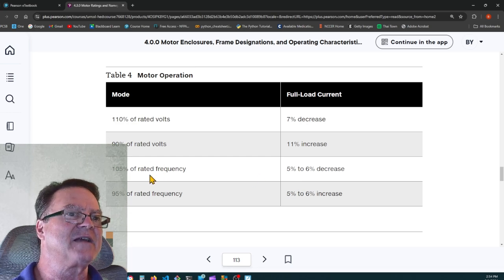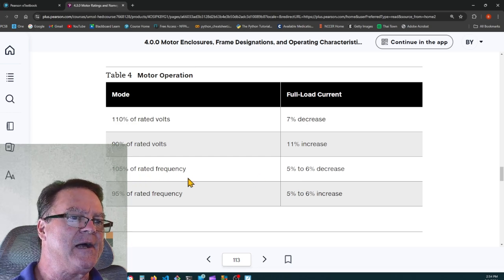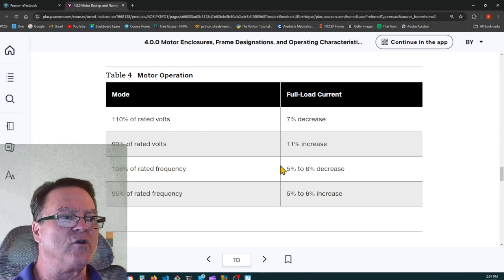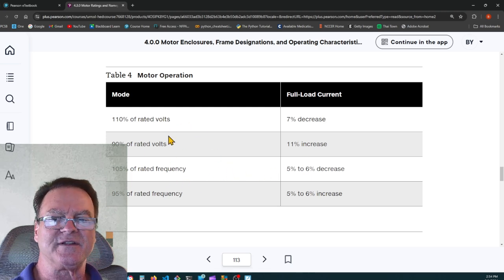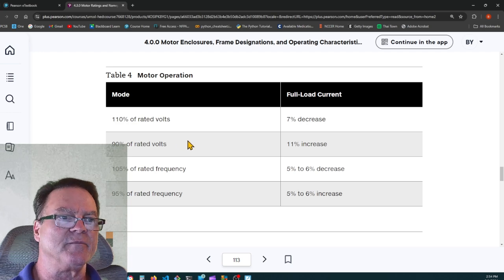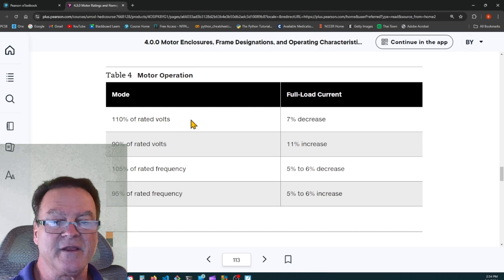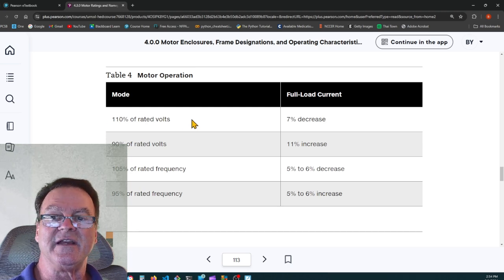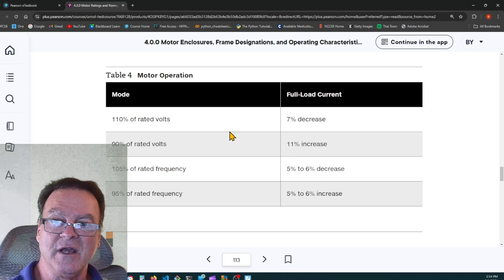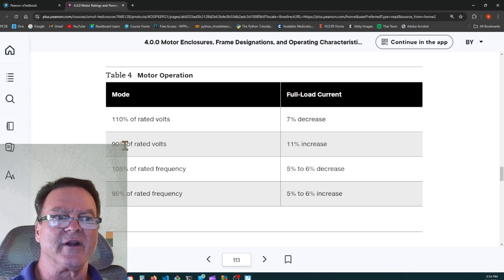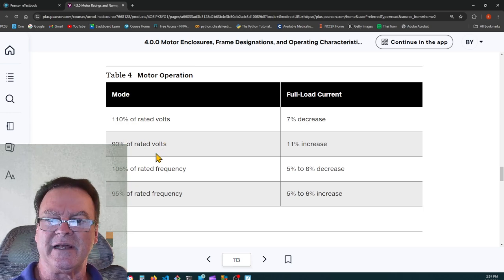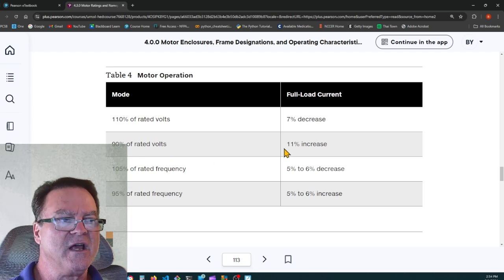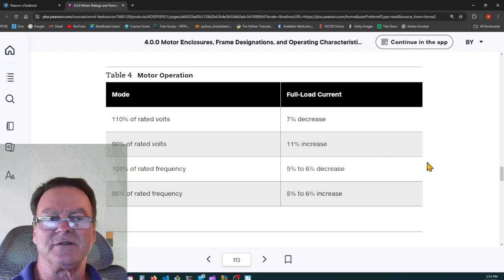So it's funny. It's kind of counterintuitive because we're thinking of Ohm's law. We think that if we increase the voltage, we're going to increase the current, but that's not true. If we increase the voltage, we're going to increase the speed of the motor, which is going to increase the counter-electromotive force, which is going to reduce the overall current. If it's running at only 90% of voltage, it's going to be running slower. It's going to be producing less counter-electromotive force. The current's actually going to increase.